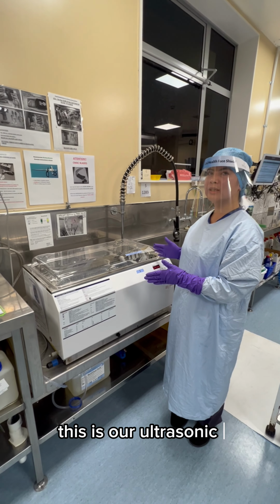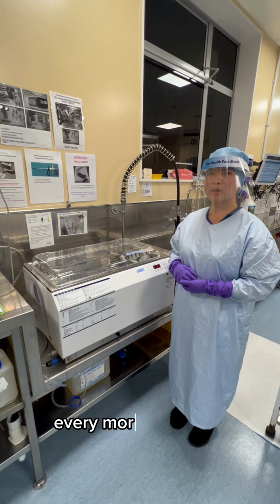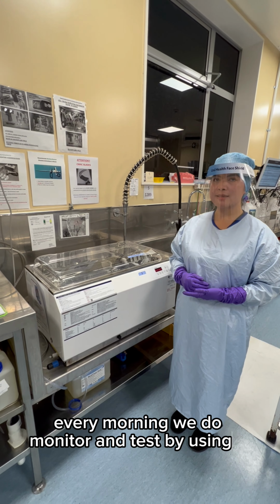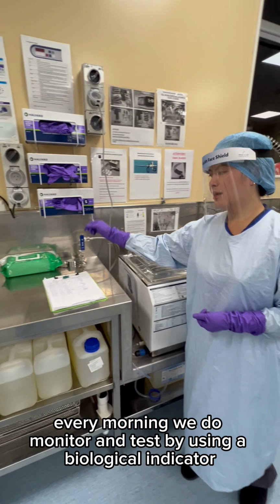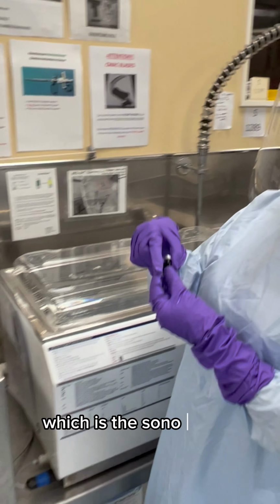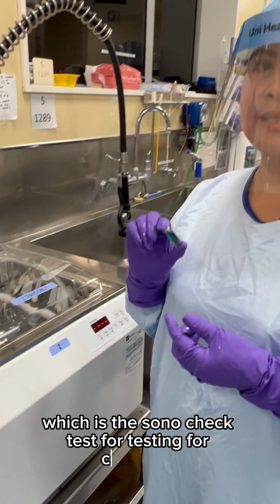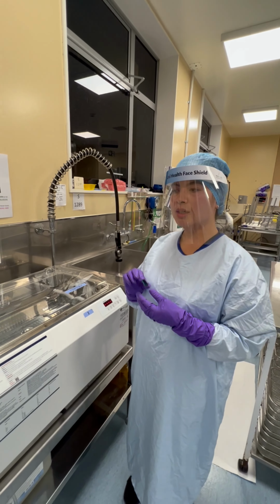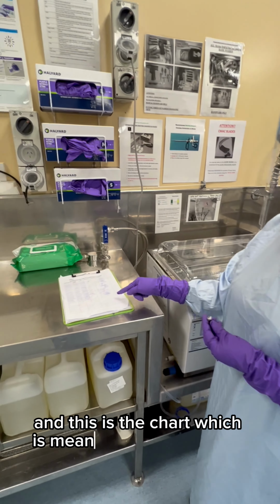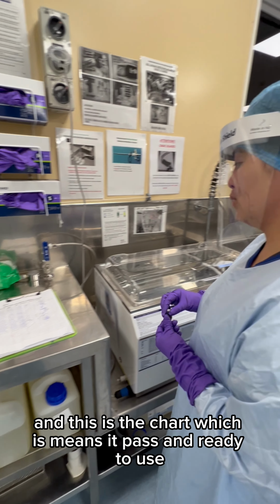This is our ultrasonic cleaning tank. Every morning we monitor and test using a biological indicator, which is the Sonocheck test for cavitation. And this is the chart, which means it passed and is ready to use.